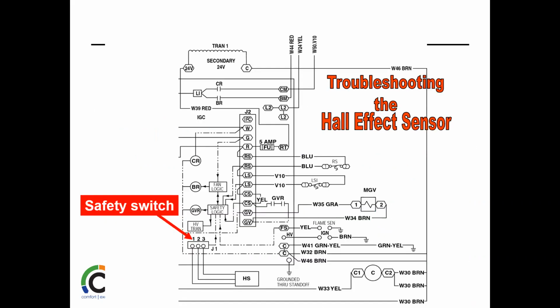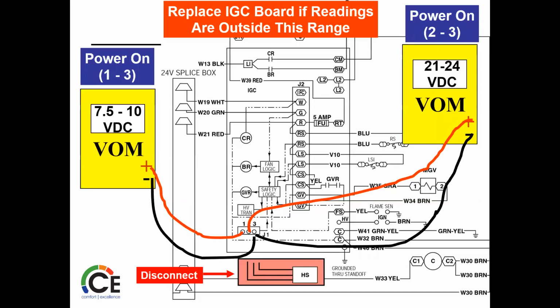So again, we're talking right here. This is the 1, 2, 3 are showing is where that wires into. That's your Hall effect switch wiring. So here's that first test. We're looking to make sure the IGC board is good. We're testing between 1 and 3. Yep, we got our 7 to 10. Then we're testing between 2 and 3. We got our 21 to 24. All right, so we're inside that range. We're saying, all right, at this point, our IGC is fine.